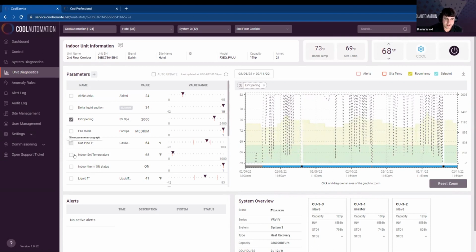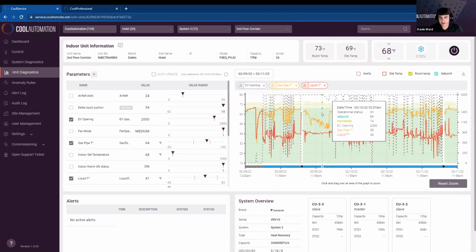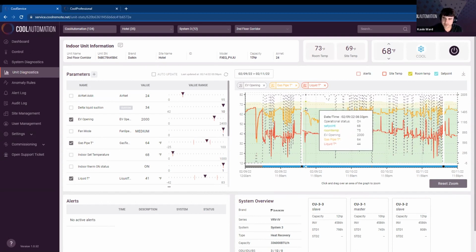So we also want to select our gas and liquid temperatures here. And right away we can tell the system is not able to satisfy the set point for this corridor. You can see that there is about a 20-degree delta from the liquid coming in versus a 65-degree temperature leaving the coil. That seems okay, but the valve position at 2000 is fully open. So this fan coil is giving it everything it's got, and it's unable to satisfy the space. And this typically indicates a shortage of refrigerant or a lack of capacity for this fan coil to satisfy that set point.